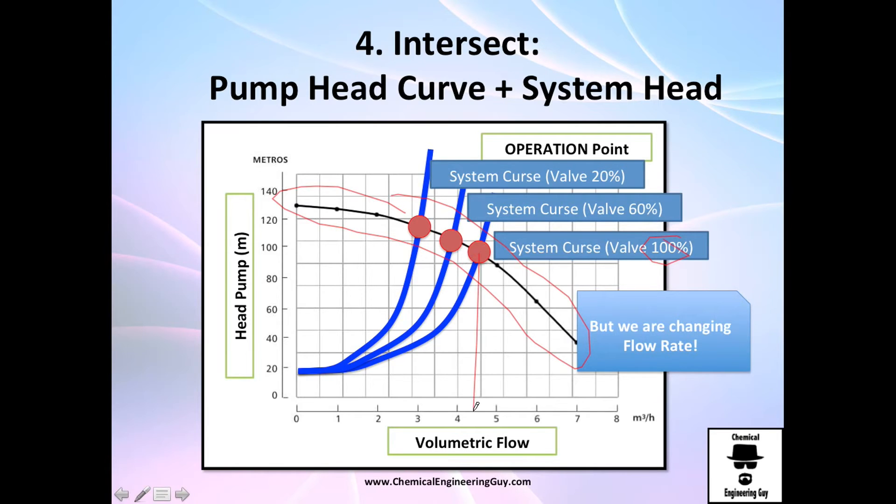For example, 100% will give you 5.5 cubic meters volumetric flow rate, 60% closed or open will give you 3.8 cubic meters, and 20% will give you only 3 cubic meters volumetric flow rate. Hopefully it makes sense to you guys that as we increase friction, we are going to deliver less volumetric flow rate with the same pump.